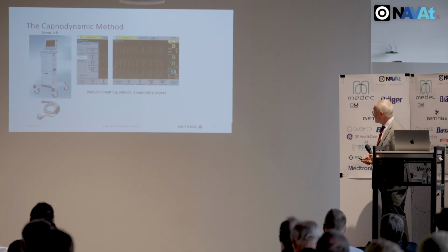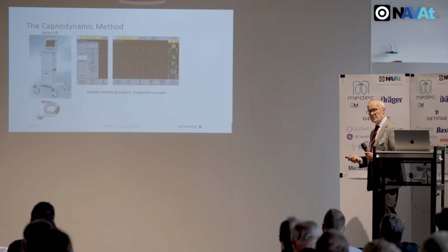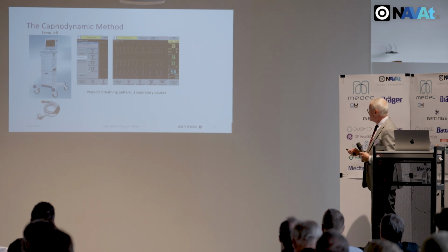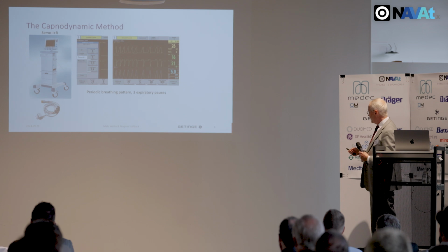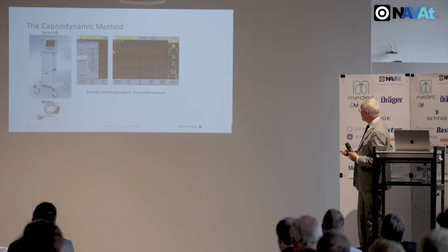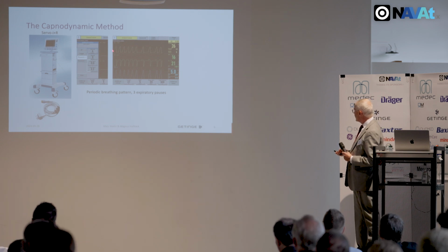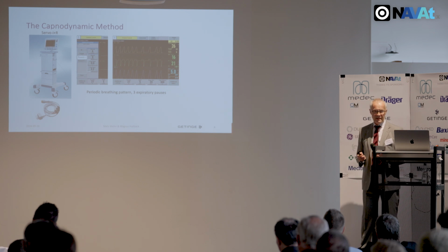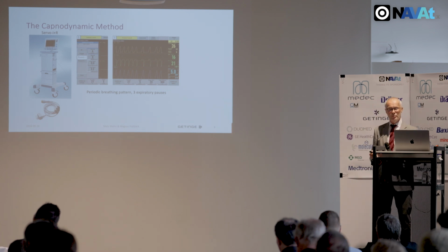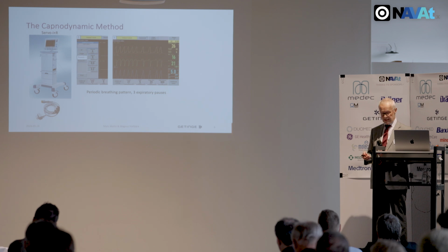So we have this ordinary Servo-i ventilator, which we have CE marked with an R, because we are now able to introduce a special breathing pattern, which you can see over here. It's a little bit dark, but we have 3 breaths with an extended expiratory pause. Otherwise, we have 6 normal breaths.